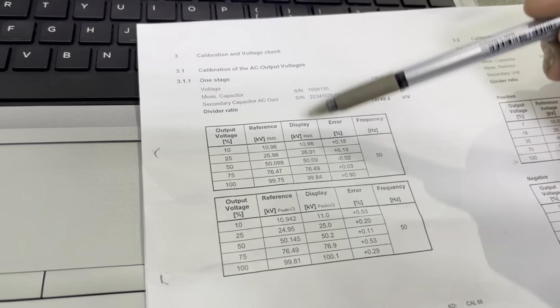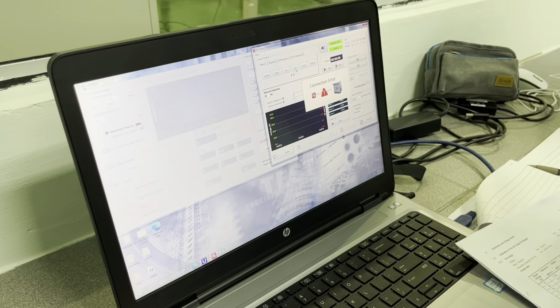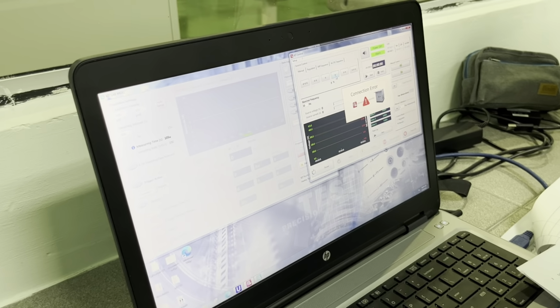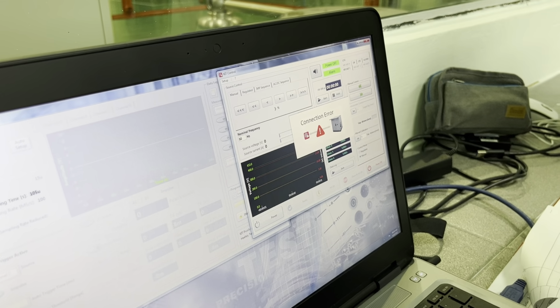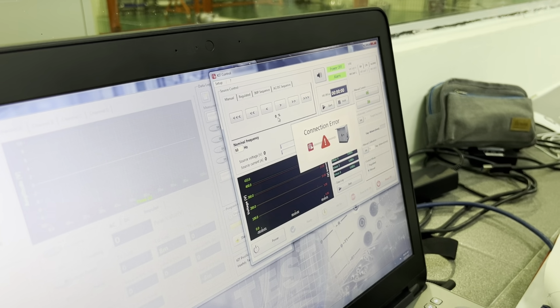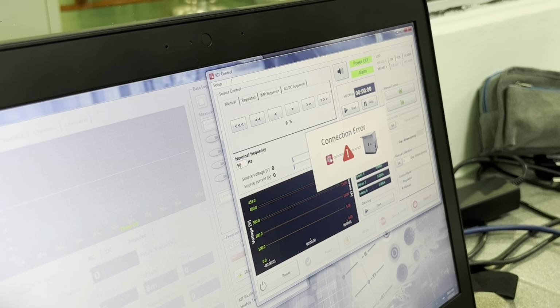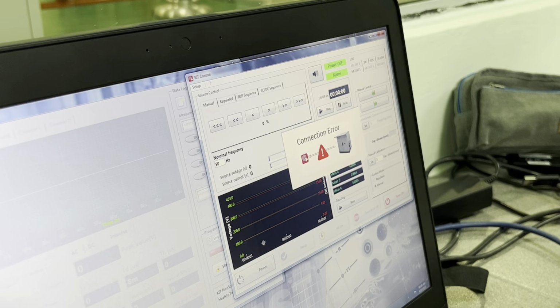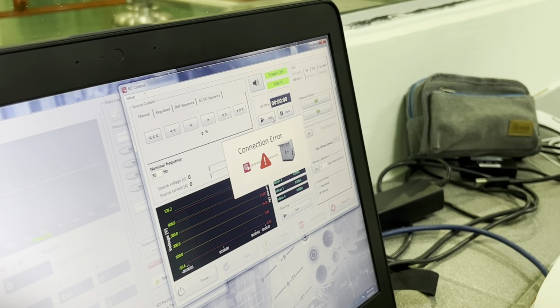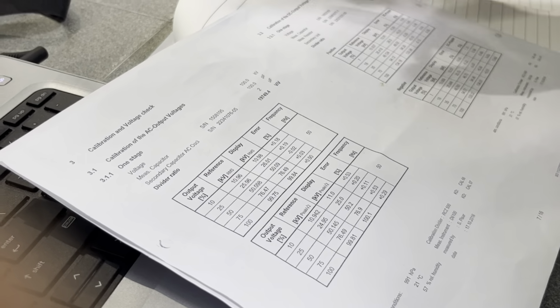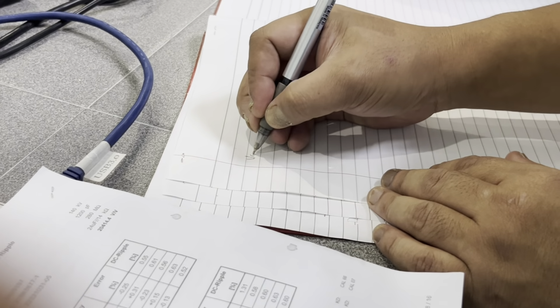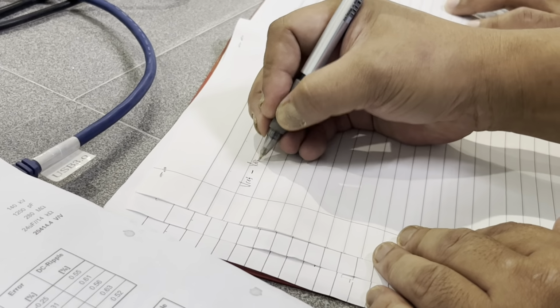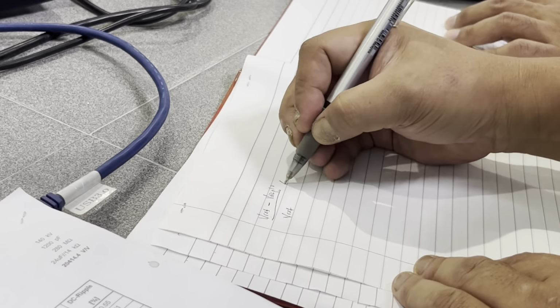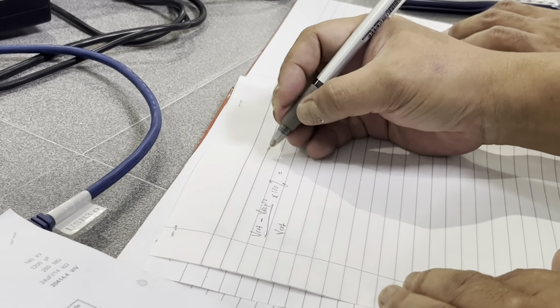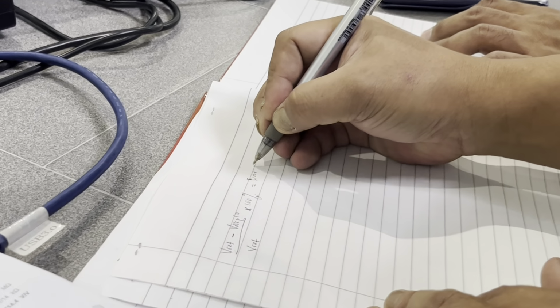Okay, now we will set our calibration value. First, we change the value until it changes to 10%, 25%, 50%, and 100%. This is the nominal frequency. Make sure it is 50 hertz, and later on we can get our result, which is here, and we should put the result in our table like this one, and we should measure the error. The error should be V reference minus V display over V reference times 100. There we will get the error percentage.